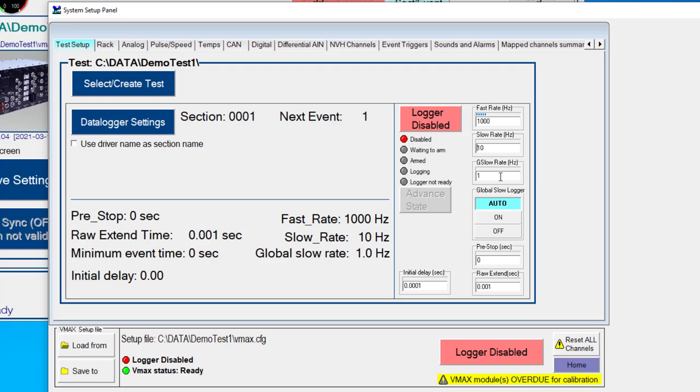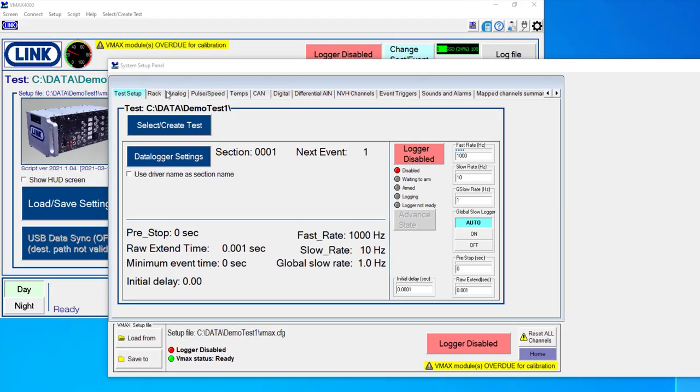Now we also have something called global slow rate. Now global slow is more like a continuous recording of signals, and that can be done whether we are actually collecting event-based data or not. So for example, anytime the logger is turned on and enabled, it could be logging global slow data on any channels that we wanted to, so we could see things that happened in between the events that we actually recorded.